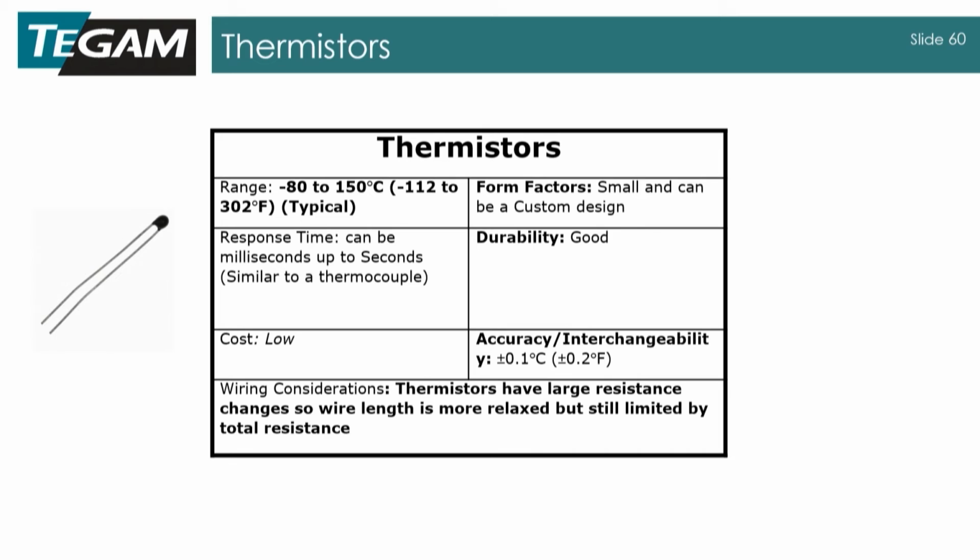Another benefit of a thermistor is that it's actually quite interchangeable, so it will repeat. Again, back to accuracy versus precision, if you can measure it and say at 75 C it produces this resistance, you'll be able to get something like 1/10 of a degree repeatability, and that's useful in certain applications. They're fairly durable too. We have some sensors that have been out 20, 30 years, and the thermistor still behaves the way it did 20 years ago, which is really useful.